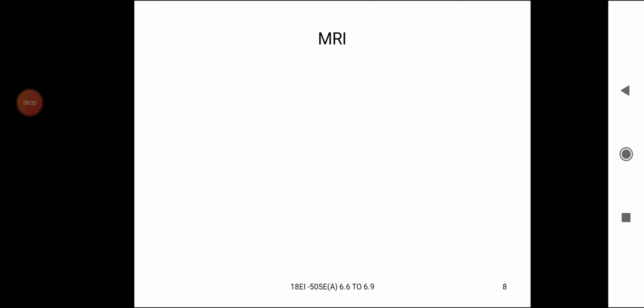This radio frequency signal is amplified by using an RF amplifier and signal averaging device and interfaced to the computer. The computer generates the magnetic resonance image of the system by using the Fourier transforming technique. It will provide an MRI image.